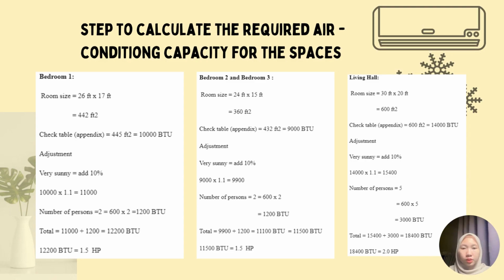This slide shows the steps to calculate the required air conditioning capacity for the space. Firstly, we need to determine the room square footage and check the recommended cooling capacity from the table and make the adjustments as necessary, such as for a heavily shaded room, a sunny room, or the number of occupants. Then find the total BTU and check the BTU requirement.